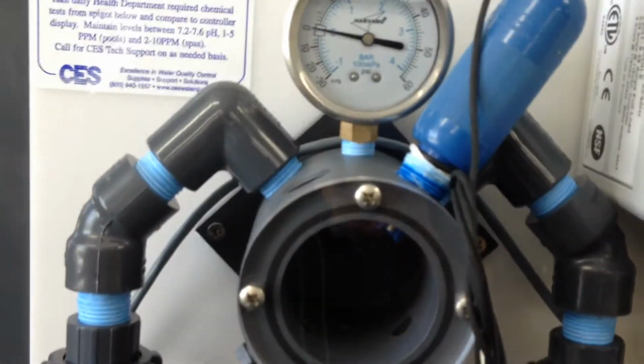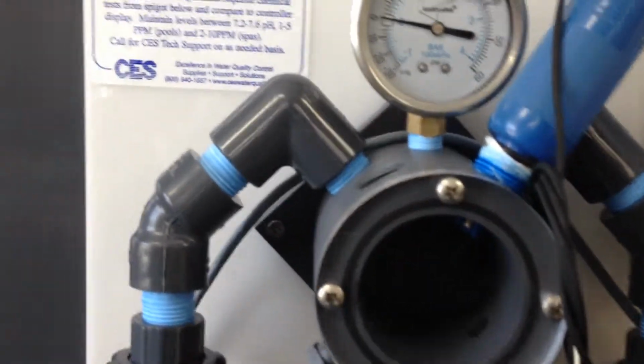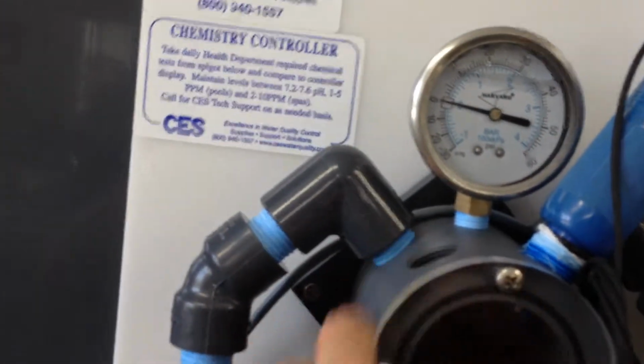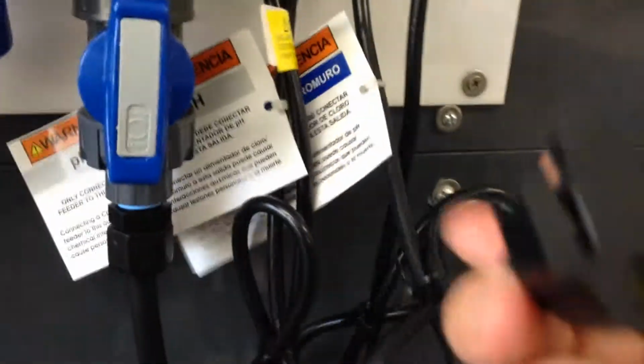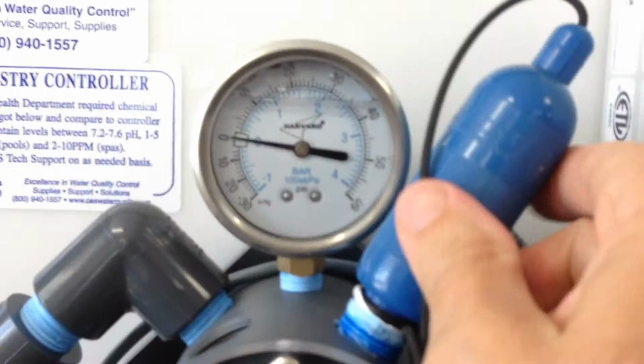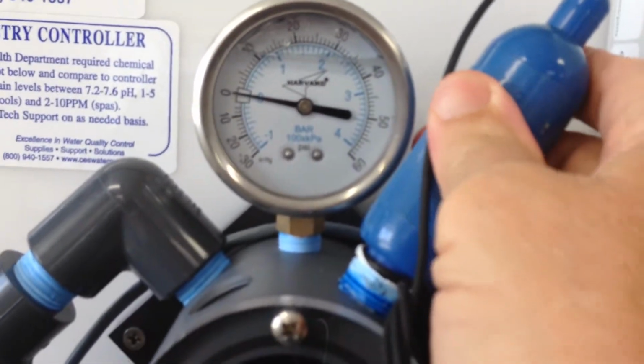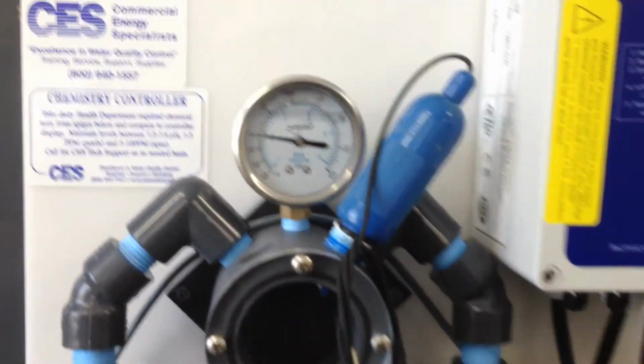And if you can get that done and run water through it, once you're confident that the probes are settled in, you plug the pH feed system into the gray, which corresponds with the gray pH probe, and you plug the pulsar solenoid into the blue, which corresponds with the blue ORP probe. So that's it in a nutshell.